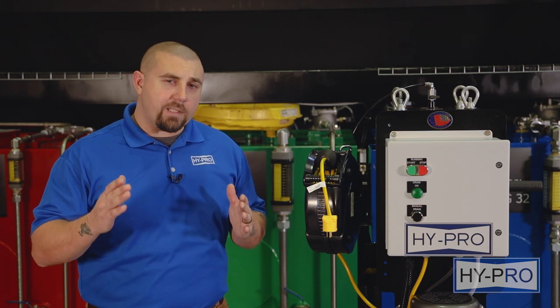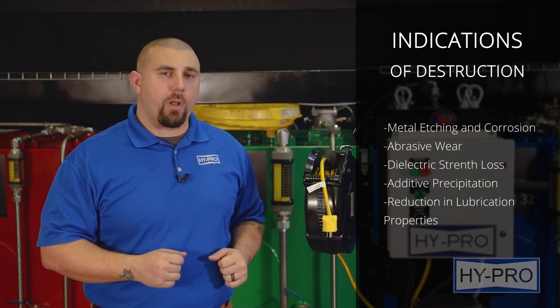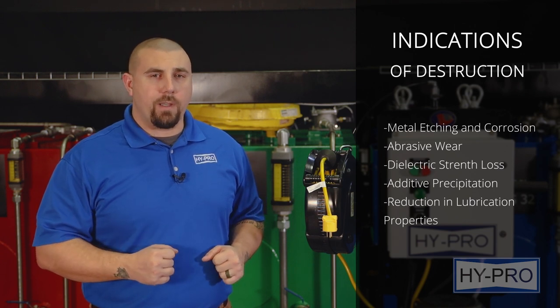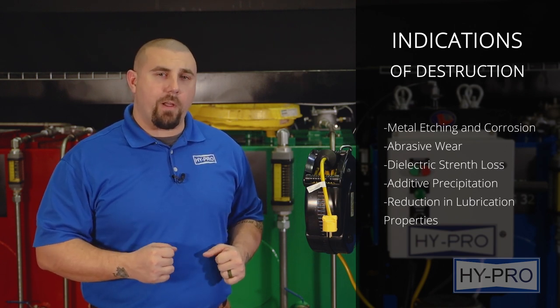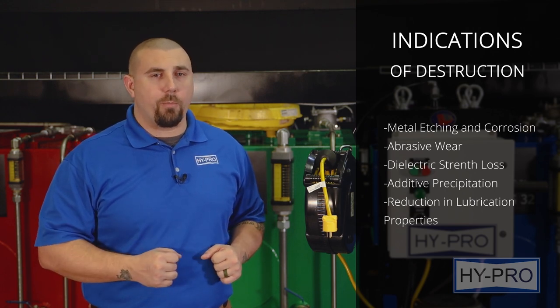Hy-Pro's coalescing technology has a focused and driven purpose, and that is the removal of free water in your systems. Some indicators that you may have high water levels causing destruction in your system could include metal etching or corrosion, abrasive wear in your hydraulic components, dielectric strength loss, additive precipitation and oil oxidation, and an overall reduction in your system's lubricating properties.